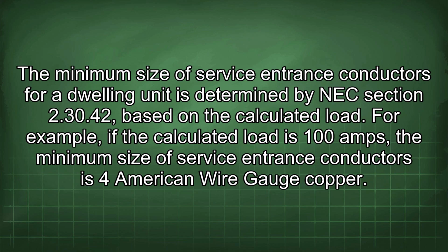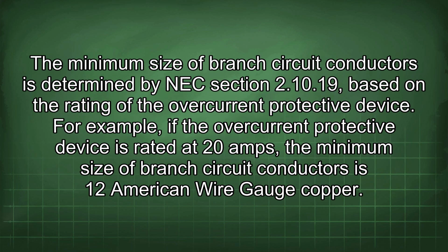The minimum size of service entrance conductors for a dwelling unit is determined by NEC Section 230.42 based on the calculated load. For example, if the calculated load is 100 amps, the minimum size of service entrance conductors is 4 American wire gauge copper. The minimum size of branch circuit conductors is determined by NEC Section 210.19 based on the rating of the overcurrent protective device. For example, if the overcurrent protective device is rated at 20 amps, the minimum size of branch circuit conductors is 12 American wire gauge copper.